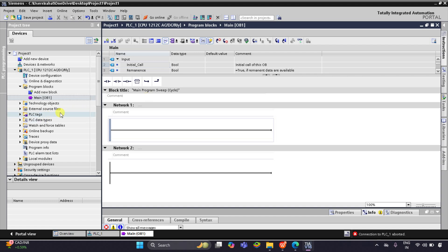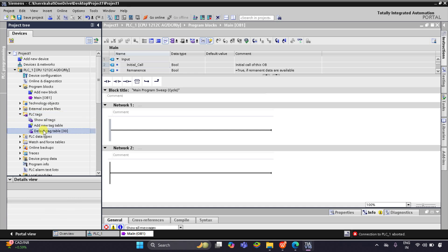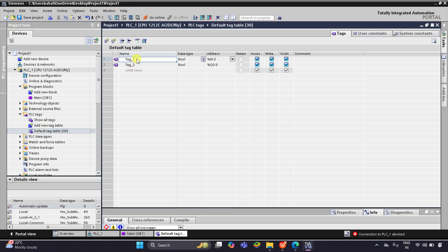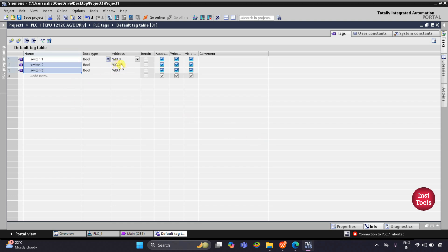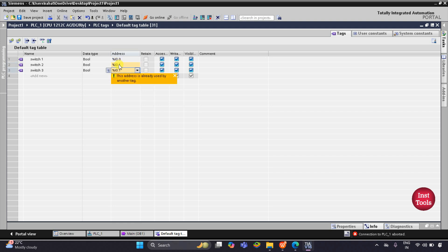This is the interface of TIA Portal version 16. Let's go to PLC Tags and then the default tag table. Let's add the inputs and outputs. For input I will add switch 1 at I0.0, then switch 2 at I0.1, and then switch 3 at I0.2.